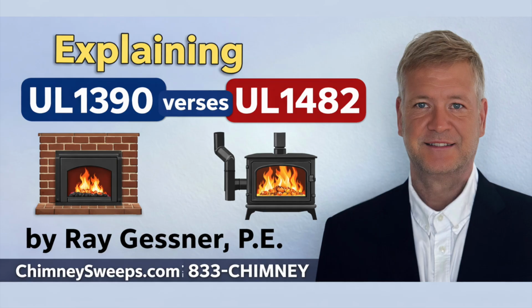I mean, you're subjecting old brick and mortar to a level of thermal stress it was never originally engineered to handle. Which is exactly why UL1390 demands such specific physical interventions. Because you're absolutely right, you cannot just drop that modern engine into the old chassis and hope for the best. And that brings us to a really specific rule in the text that outlines exactly how you have to handle the exhaust. UL 1390 requires venting through the throat or damper area of the masonry fireplace, but it mandates testing with a, and I'm quoting here, "continuous chimney liner from the appliance collar to the point of termination."